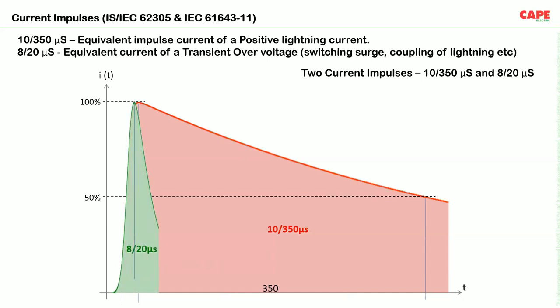Similarly, we have the 8 by 20 microsecond waveform also. And you can see that in the first 8 microseconds, it reaches its peak. And in the next 20 microseconds, it comes down to half of its crest value. From the waveform, it is very clear that a lightning impulse has a very high specific energy and charge. So it can create more damage to your electrical system when compared to an 8 by 20 microsecond impulse.